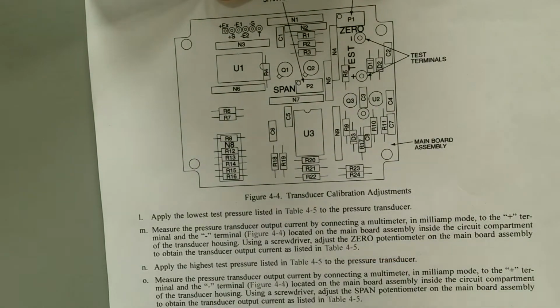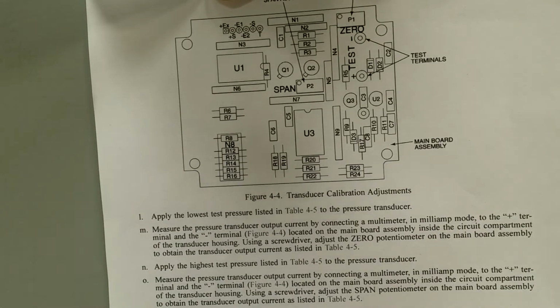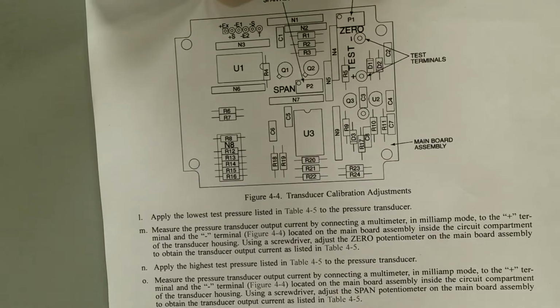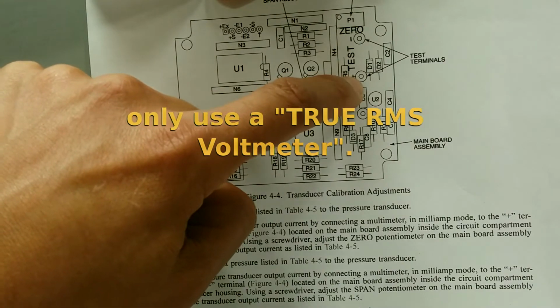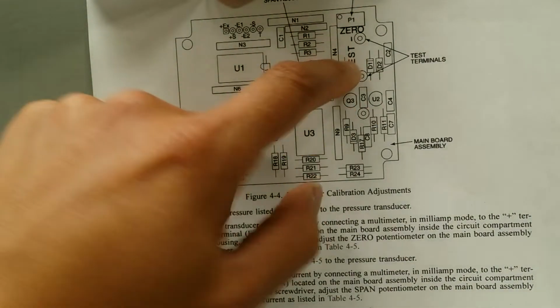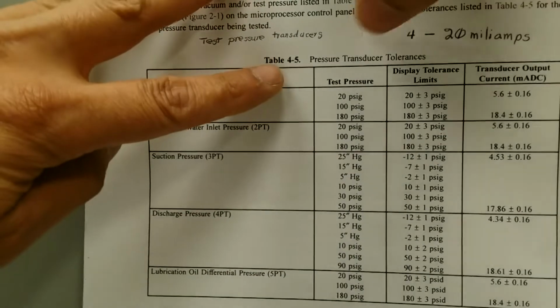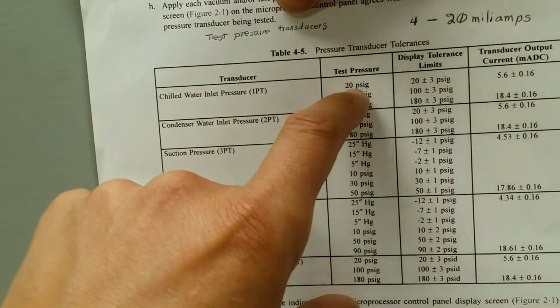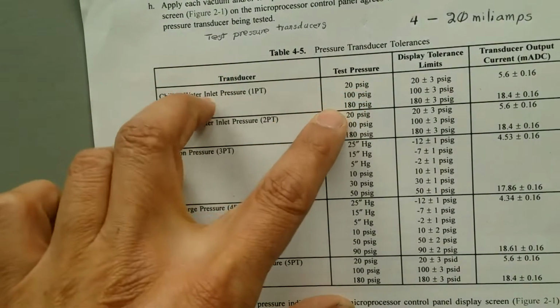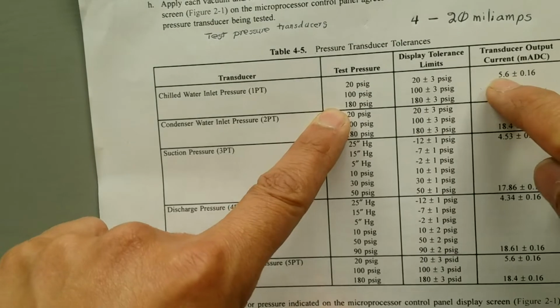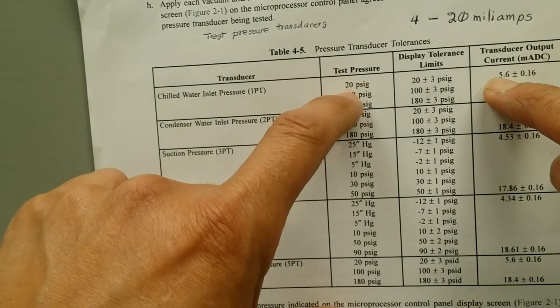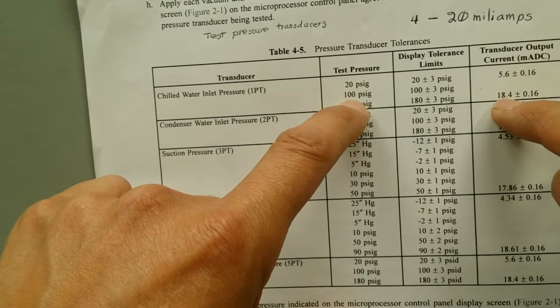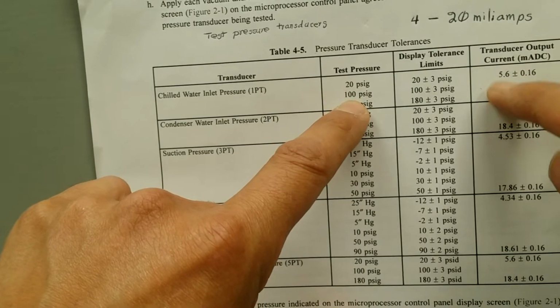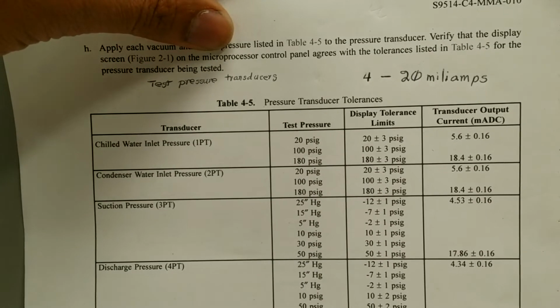Then you leave the multimeter in there. You don't touch it, you don't remove it, and you switch the multimeter to the current setting and start reading, obviously, milliamps. You switch your multimeter from voltage to current, and you should get the values of current that correspond to the pressure over here. So at 20 psi for the chill water inlet pressure transducer, you should get a current somewhere in this range, and as the pressure increases, you should extrapolate to determine what the value in between should be.